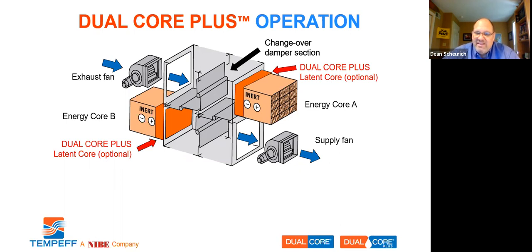And the science behind that is you never completely de-energize a core. Basically, with that stated, you will always have energy in there. You're not taking it down to what the outside air temperature is. So that is a huge benefit when you're looking at maybe supplying the back end of some other equipment that requires certain temperature air. It'll also allow you to help track better when you say reheat that air back up coming into the space.